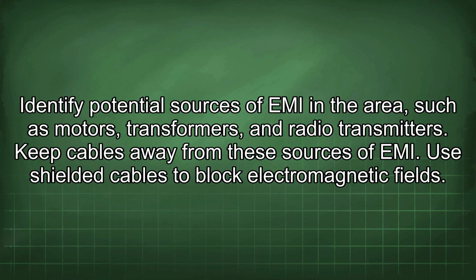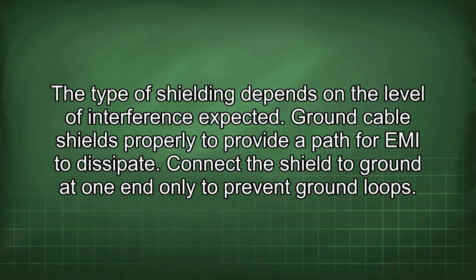Identify potential sources of EMI in the area, such as motors, transformers, and radio transmitters. Keep cables away from these sources of EMI. Use shielded cables to block electromagnetic fields. The type of shielding depends on the level of interference expected. Ground cable shields properly to provide a path for EMI to dissipate. Connect the shield to ground at one end only to prevent ground loops.